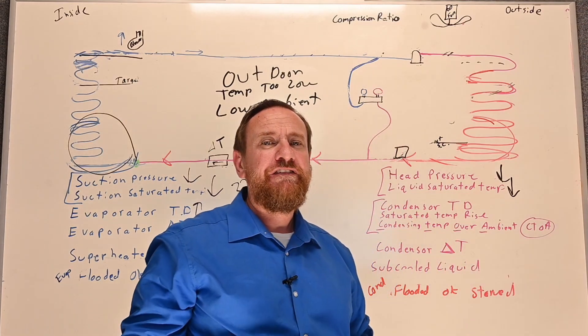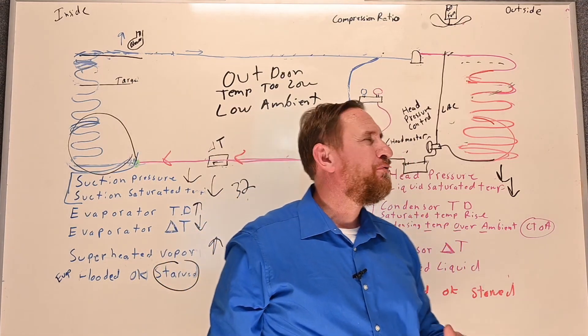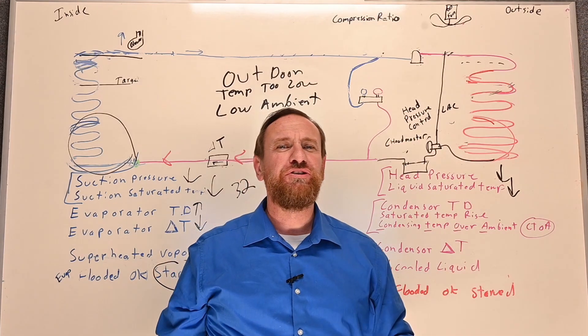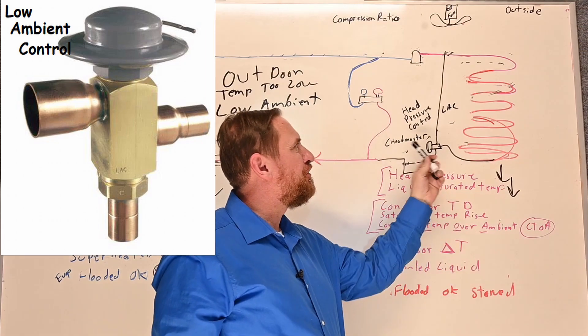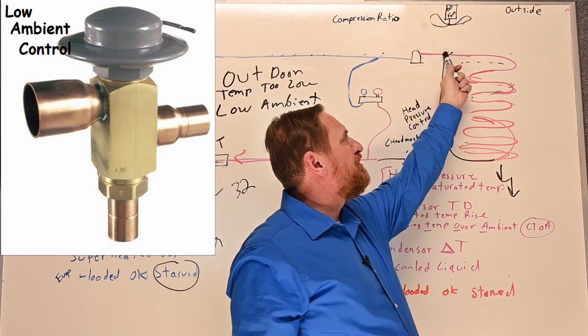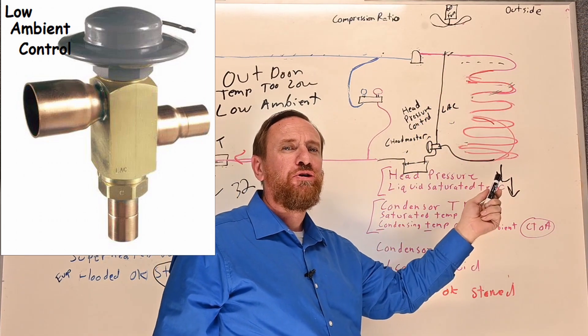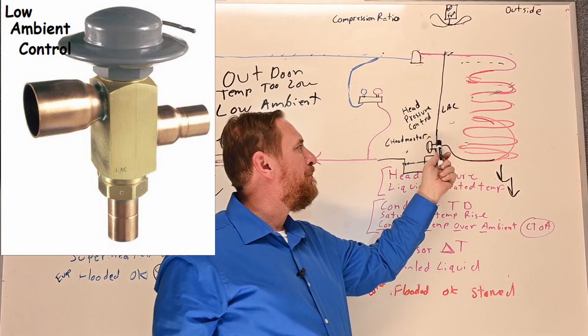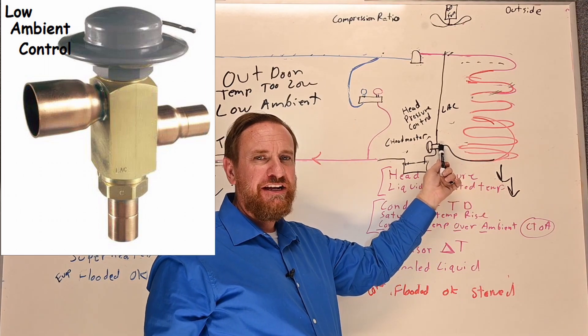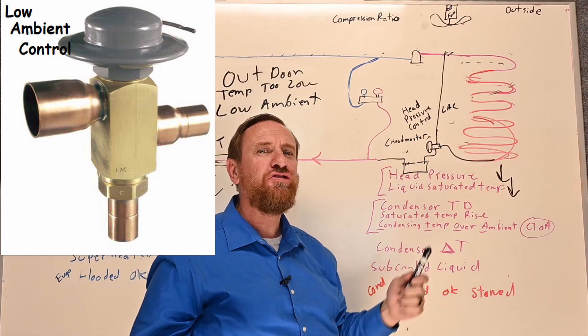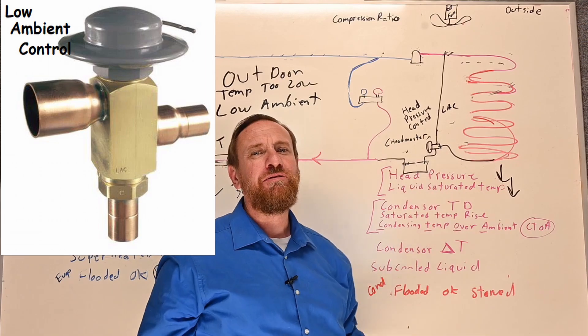And then there's my favorite way. So we can also use what we call a head pressure control. A lot of people call them a headmaster, but it's a head pressure control. The LAC is the most common type. What we're going to have is three pipes on it. We have our discharge line. It goes into our condenser like normal, but our discharge line also has a bypass option that comes down to. Then as the refrigerant comes out of our condenser, it also goes into this. And the third one comes out and either goes to our liquid line or to our liquid receiver. Most usually it's a liquid receiver.